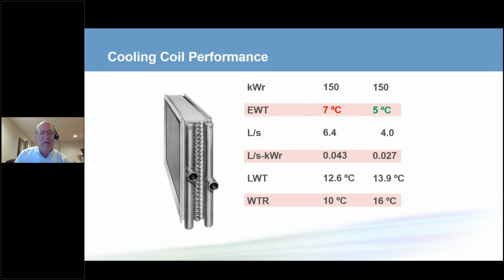One other thing that you might have to do, sometimes coil control valves are oversized. And if the coil control valve was oversized when we had a 6-degree C delta T, it's going to be even more oversized at a 9-degree C delta T. So you might want to change and retrofit some of the valves on those coils to get better control at lower flow conditions.